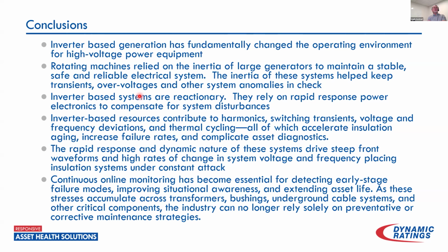So in conclusion, inverter-based generation has fundamentally changed the operating environment for high voltage power equipment, not only for transformers, but also for breakers and switchgear applications, stressing insulation in ways that we never expected before. Rotating machines relied heavily on inertia to keep the system stable. Inverter-based systems are reactionary. They rely on a rapid response of the inverters to compensate for system disturbances. When that happens, it can result in increased harmonics, switching transients, and voltage and frequency deviations, because it's reacting to what's happening on the system.